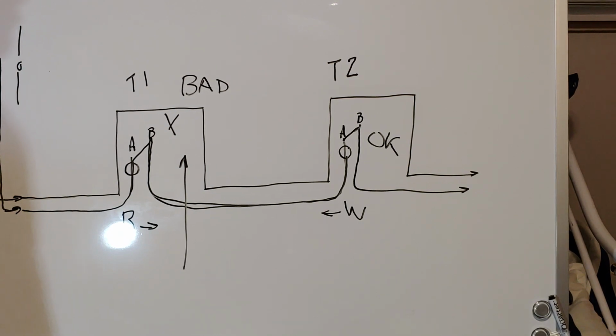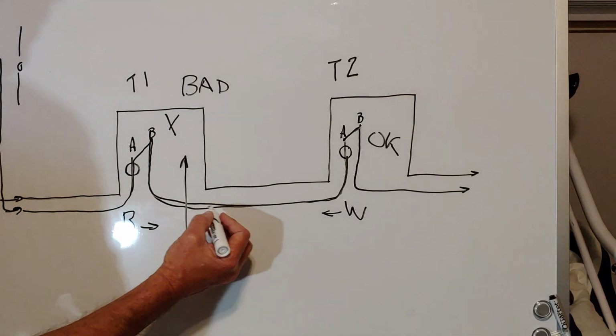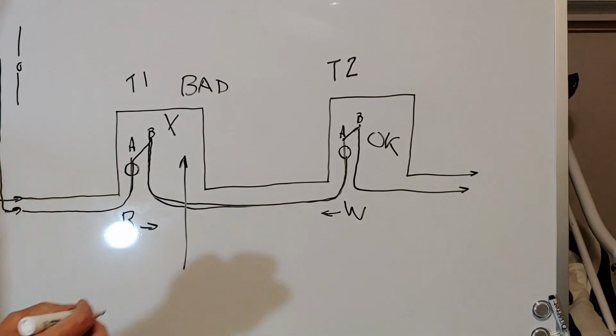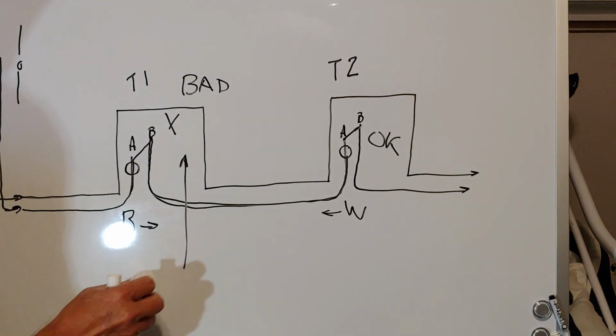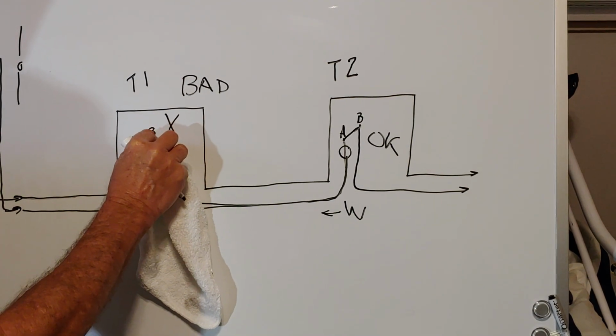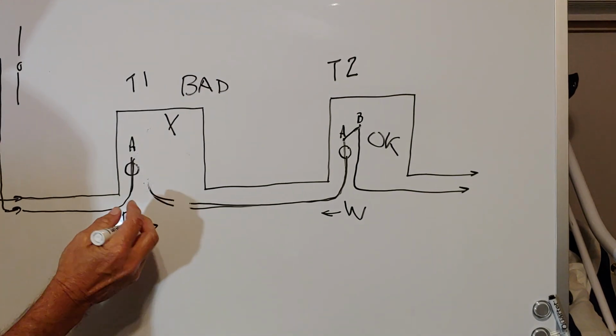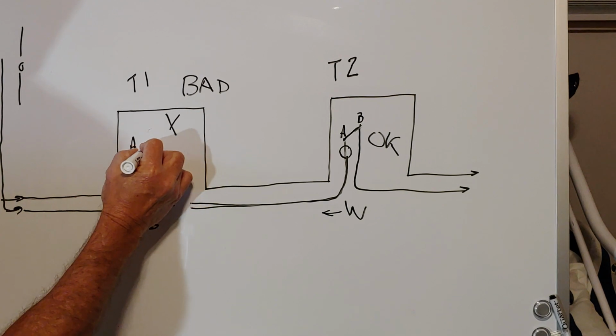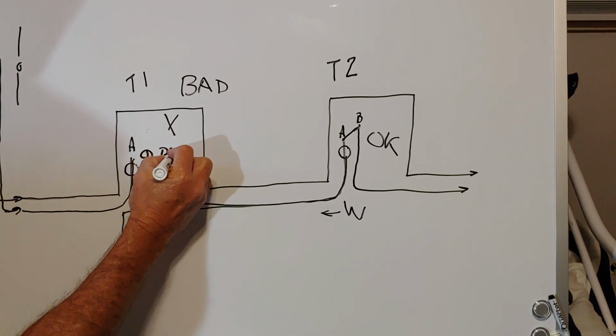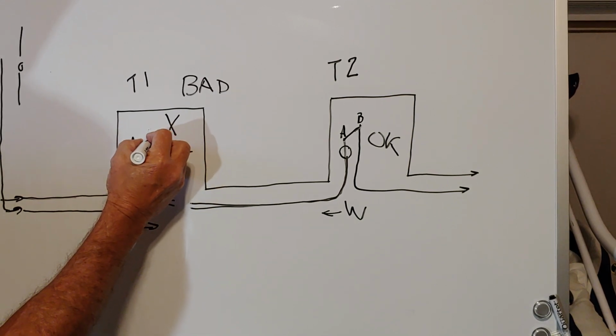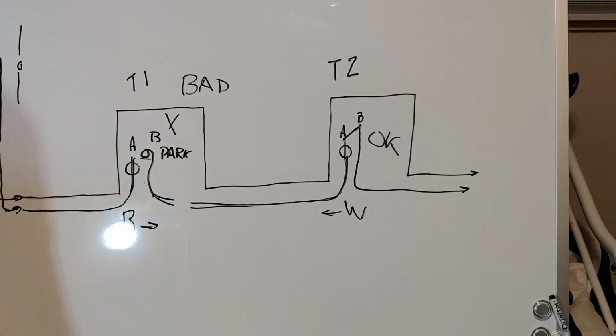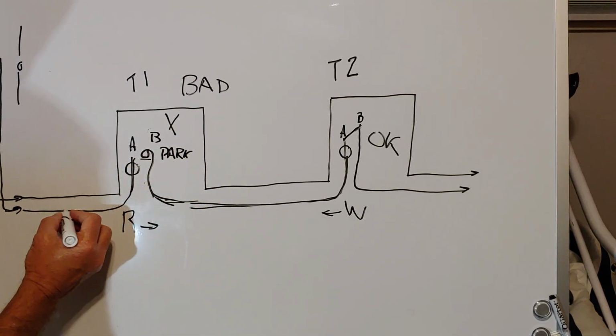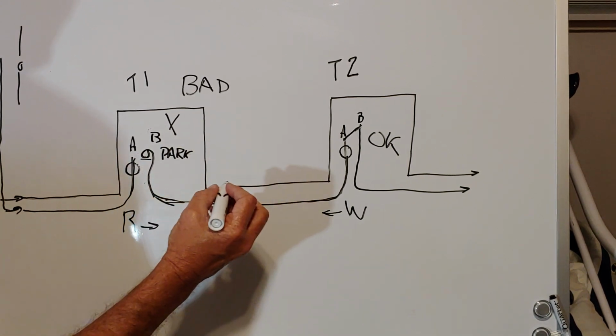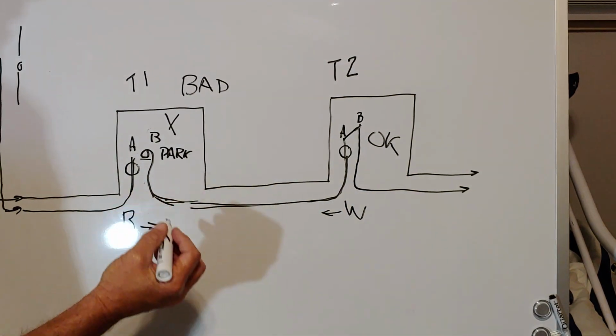Now, we don't have a testing tool with us right now to test a transformer. They do make them out there in the world. But our assumption is, because cable is the most likely problem we have in this situation, we're just going to isolate the cable. So what we're going to do here, in this situation, if this is our suspect span, we're going to come up here and we're going to park the outbound B. It comes off of B, and we're going to park it right here in a parking stand. And we've already discussed this before, what a parking stand is. So we're still feeding into the transformer. Now I won't get into isolation. We'll talk about isolation a little bit on. Remember, we're still talking about fault indicators.